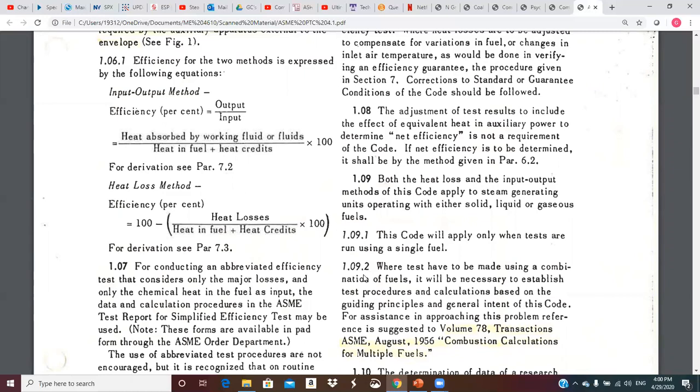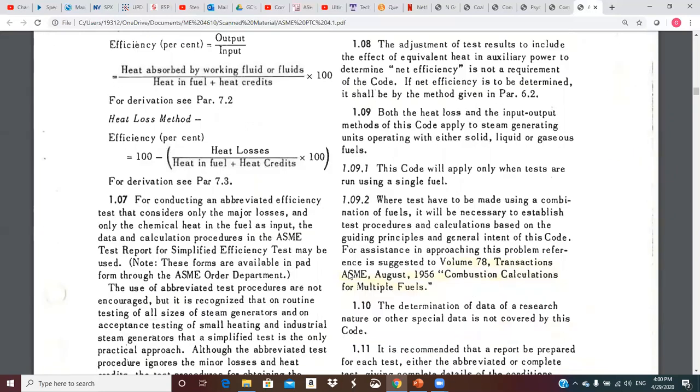And then the second way is the loss method. And that is 100% minus heat losses. And there's, I think there's, I don't know, 15, 16, 17 different losses possible. Not that a boiler will have all of them, but a big boiler might have eight or 10 of them. And that's the magnitude of that loss divided by the heat in the fuel plus the credits. In other words, the input.